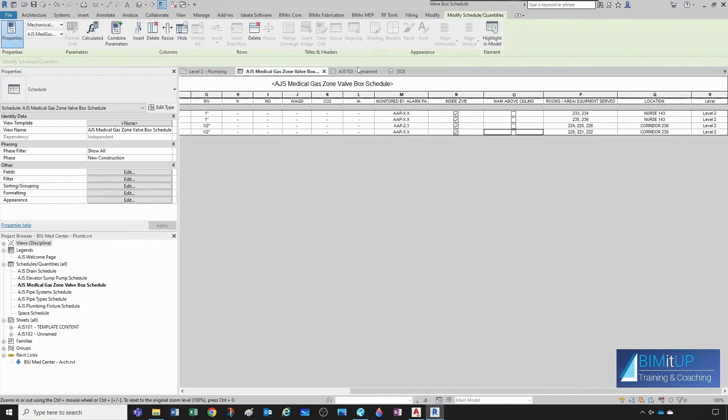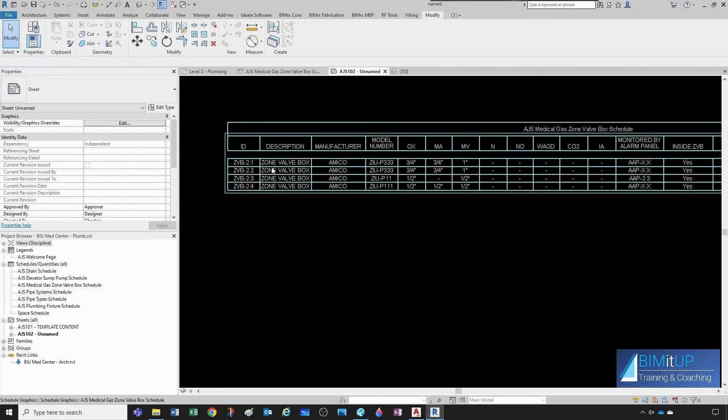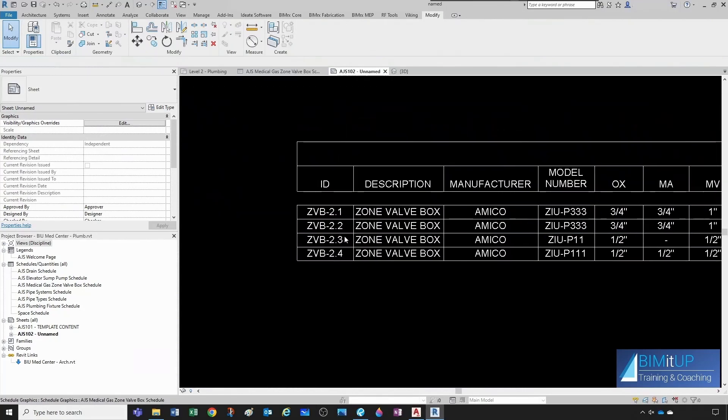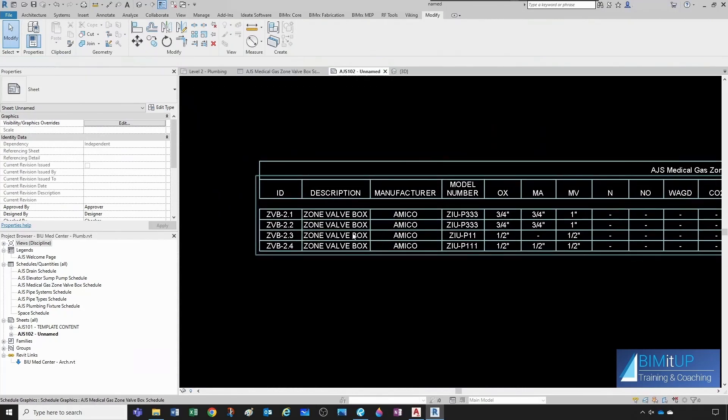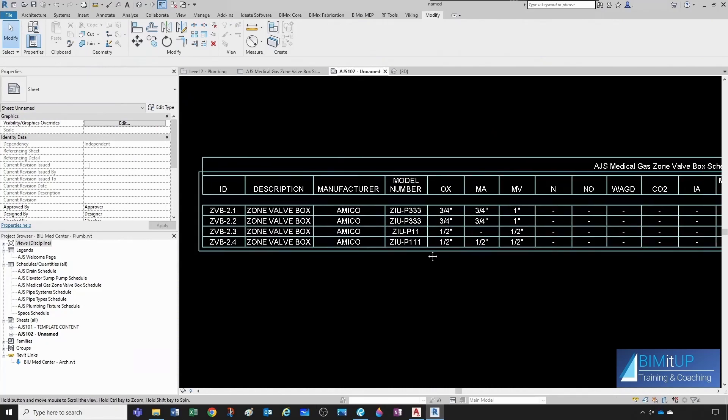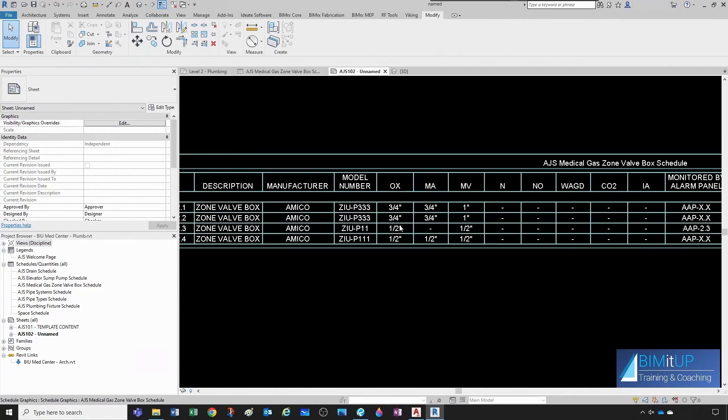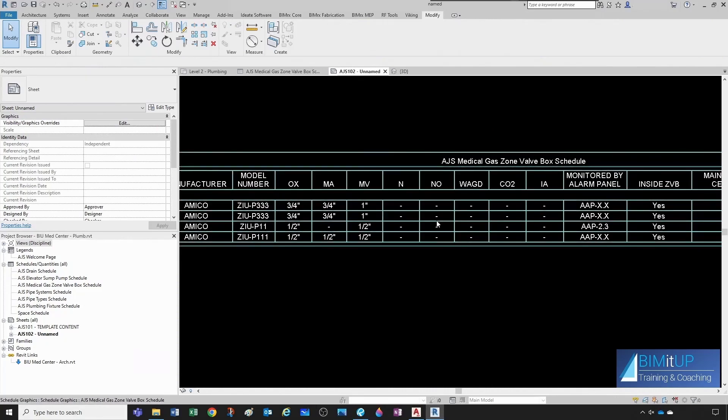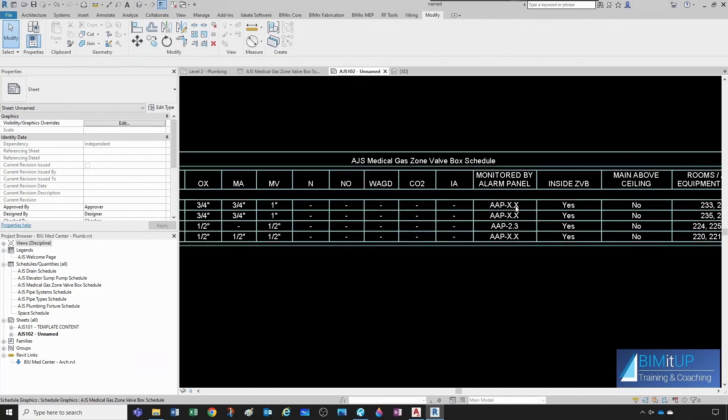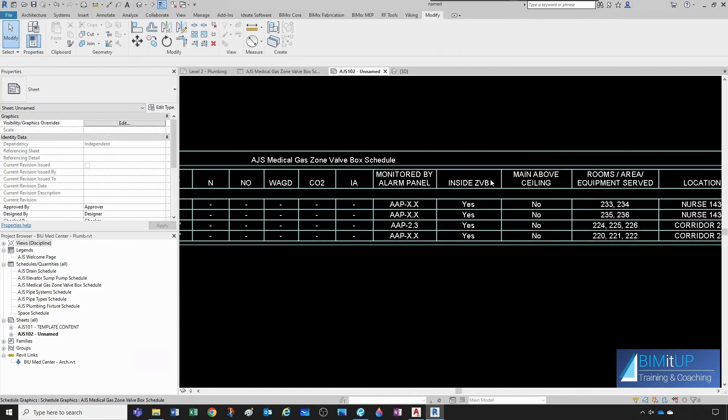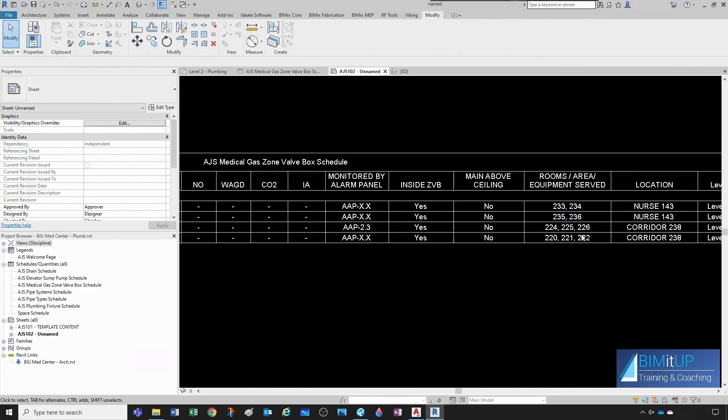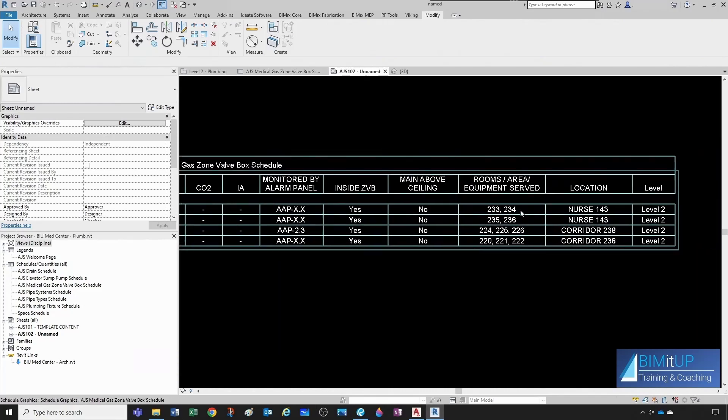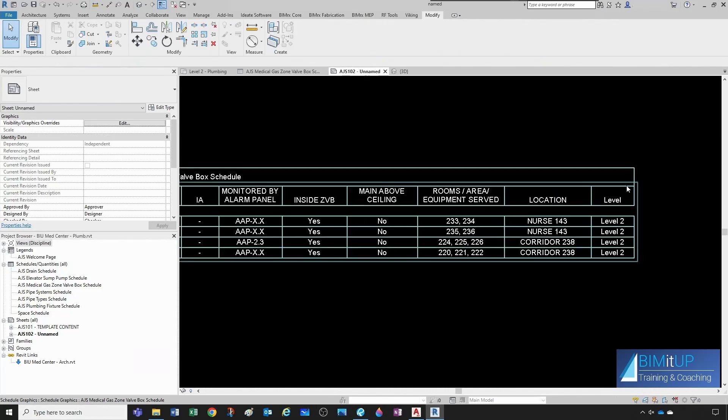Let's go to our sheet. All our IDs, description, manufacturer, model number, sizes for each one of them. Very good. The alarm panel that are monitoring that, whether they have sensor in the zone valve box or above ceiling. It would be nice to add a header here. So, let's see if we can do that. Then we have the rooms served, and the location that they're at, and the level that they're at. And this can be a hidden column.